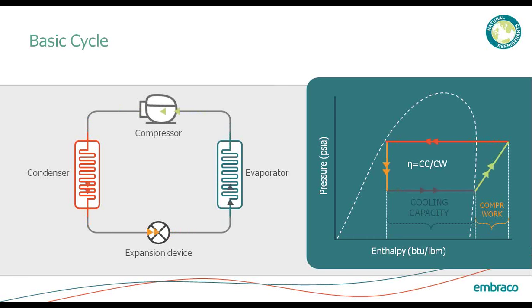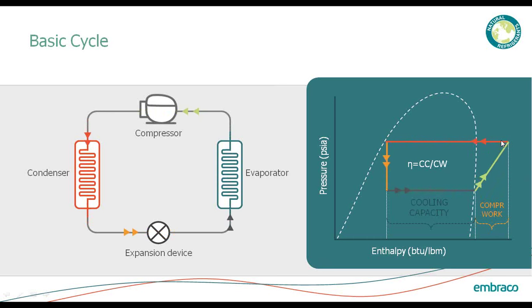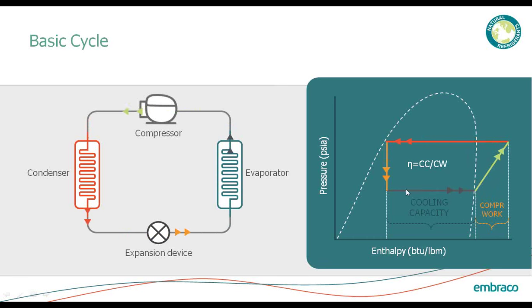This boiling of the liquid in the evaporator is what gives you your cooling capacity. Looking at it on a pH diagram: here's the compressor applying work and raising the pressure, then we enter the condenser — a constant pressure process — and reduce our temperature, then enter the expansion device and drop pressure, then enter the evaporator — again a constant pressure process — where we change phase and eventually raise temperature.